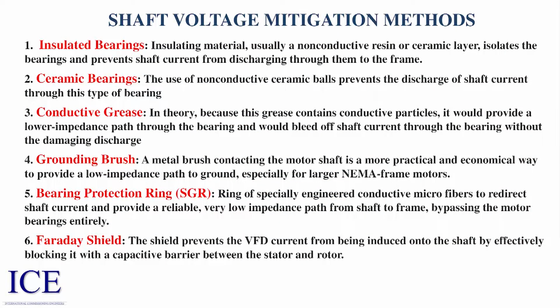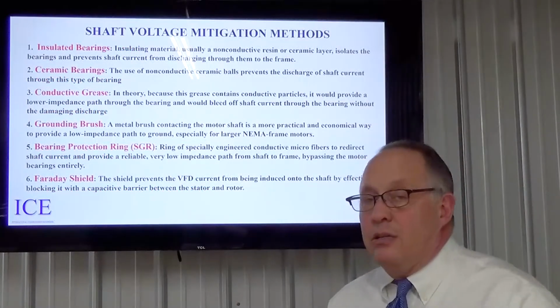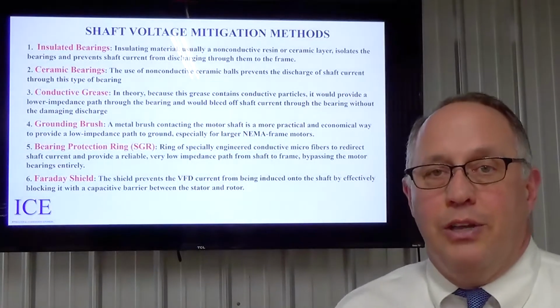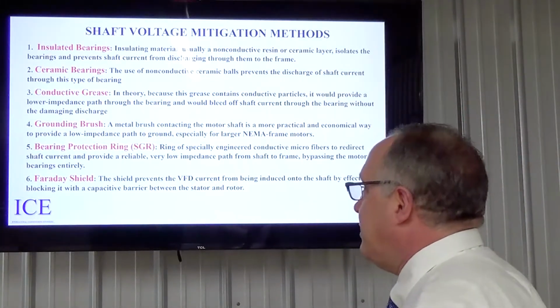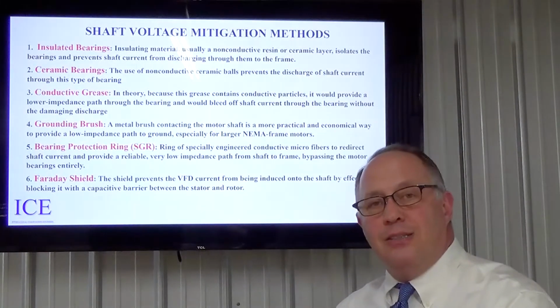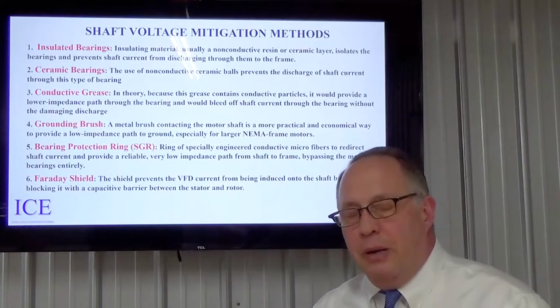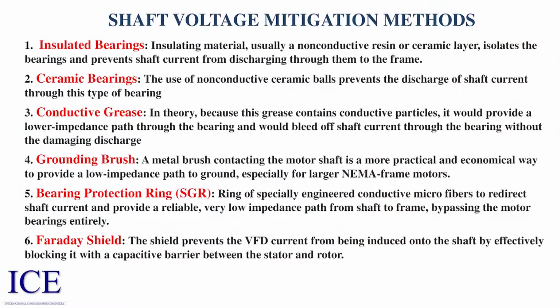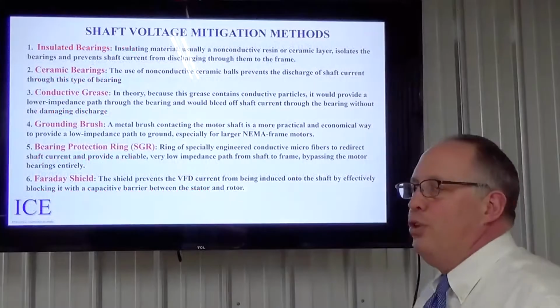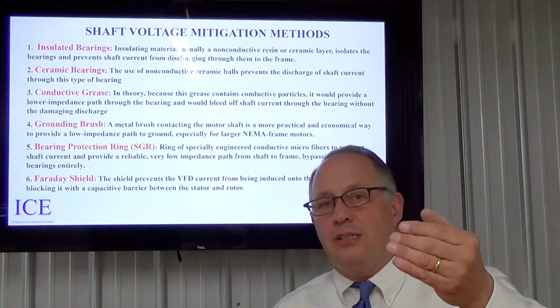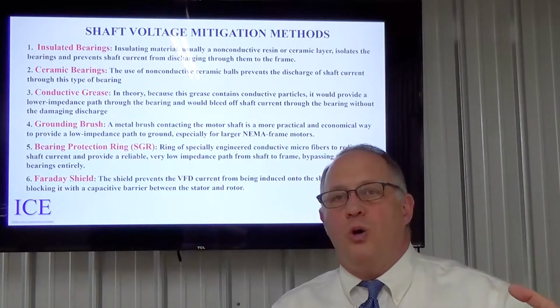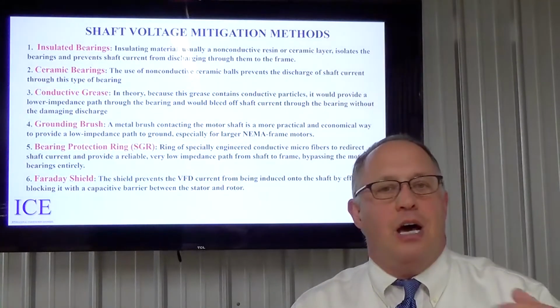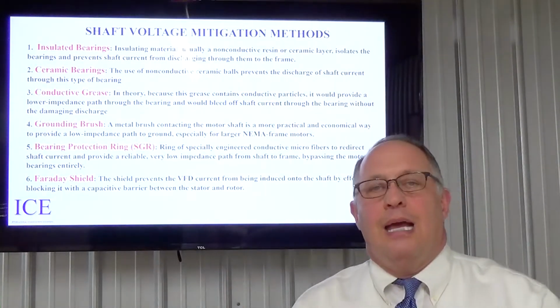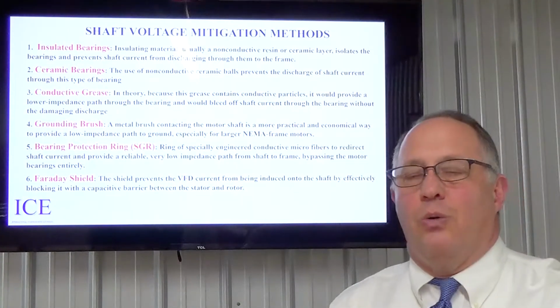Shaft mitigation methods. There are 6 common ways to get rid of this issue, solve it. Number 1, insulated bearings. So you can take and use insulated bearings, not just sealed bearings. That's not what I'm talking about. Insulated bearings, where the insulating material, along with a non-conductive resin or ceramic layer, isolates the bearings and prevents shaft current from discharging through the bearing to the frame. In other words, it's still inducing the shaft voltage, but because we've got these insulating bearings, it does not have a way to arc over and cause damage in the bearings. So it just sits there with the shaft voltage.